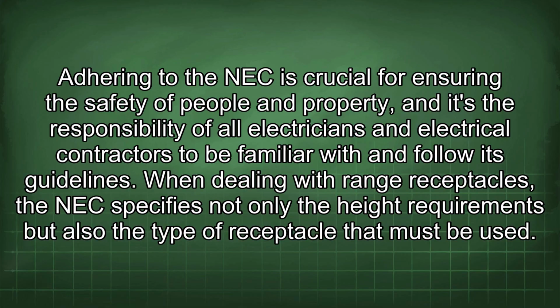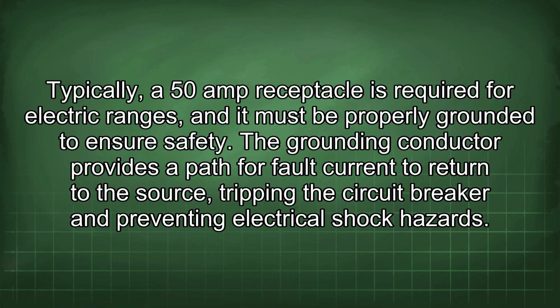When dealing with range receptacles, the NEC specifies not only the height requirements but also the type of receptacle that must be used. Typically, a 50 amp receptacle is required for electric ranges, and it must be properly grounded to ensure safety. The grounding conductor provides a path for fault current to return to the source, tripping the circuit breaker and preventing electrical shock hazards.